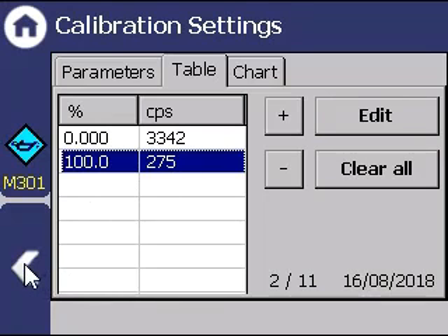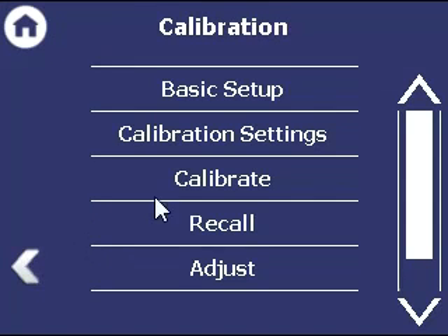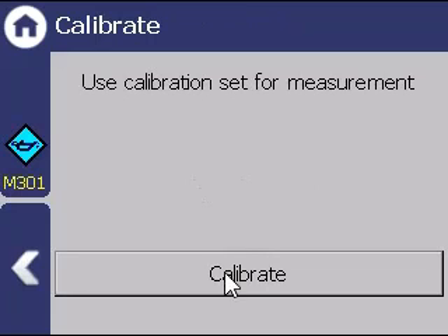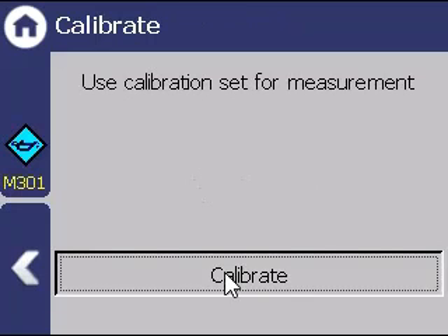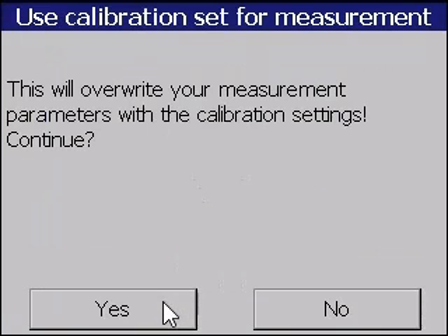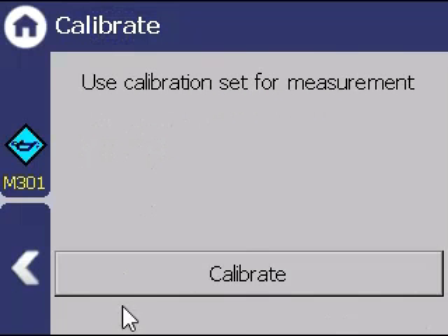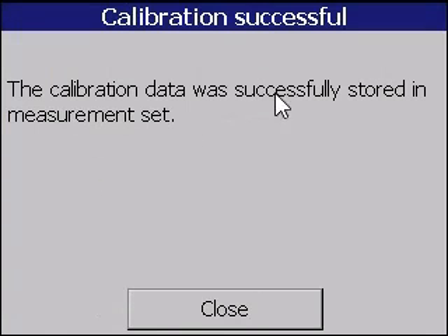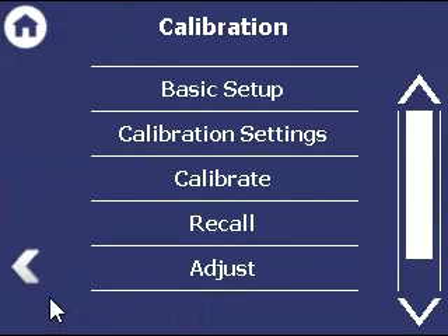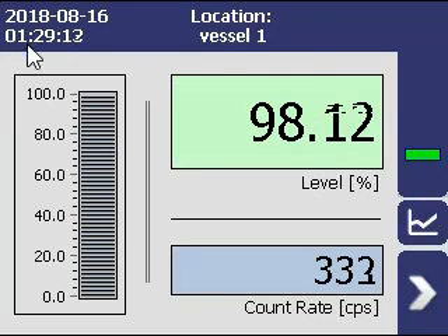We'll now press back, calibrate, calibrate again, and we will confirm that we do want to overwrite the parameters from the previous calibration with a yes. Our calibration was successful. Click Close and Home. And we see our successful calibration.